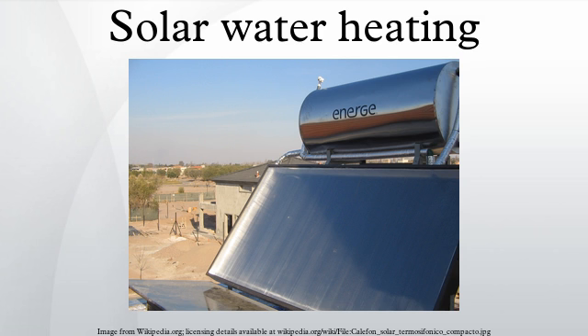The solar collectors will almost always be hot when the pump(s) are operating, and some do not use solar controllers. Sometimes, however, a differential controller is used to prevent the operation of the pumps when there is sunlight to power the pump but the collectors are still cooler than the water in storage. One advantage of a PV-driven system is that solar hot water can still be collected during a power outage if the sun is shining. Another advantage is that the operational carbon clawback of using mains pumped solar thermal is completely avoided.